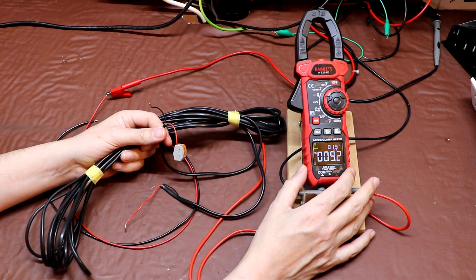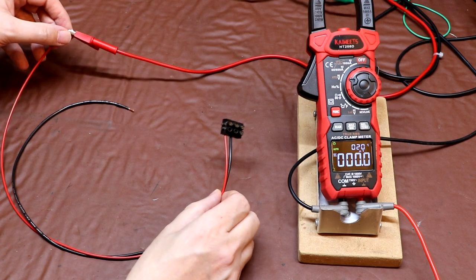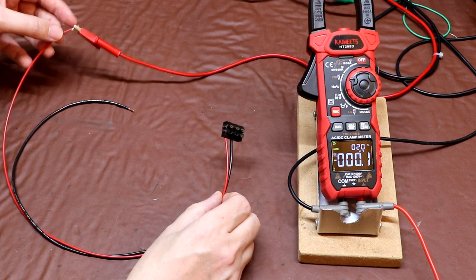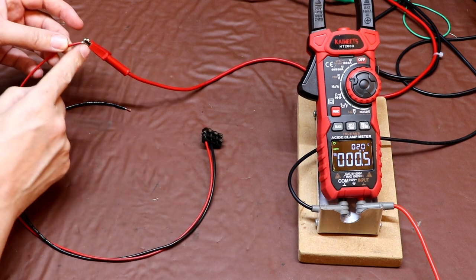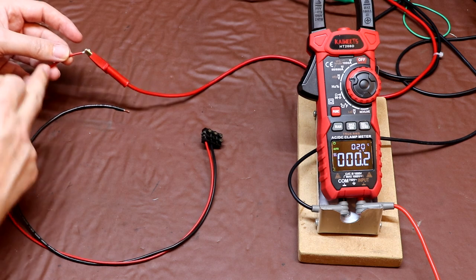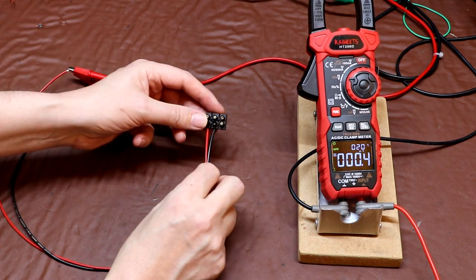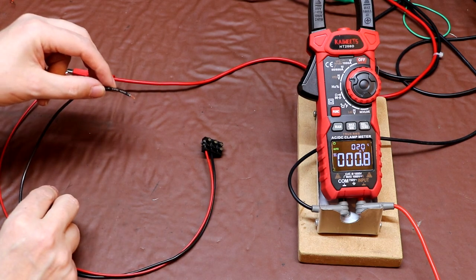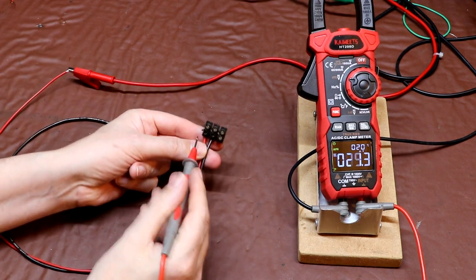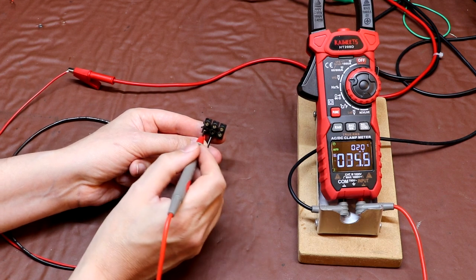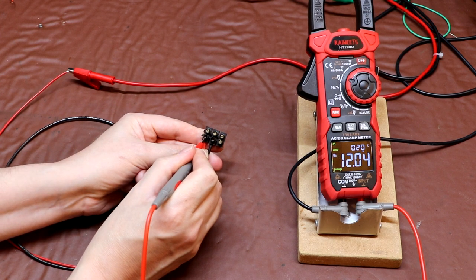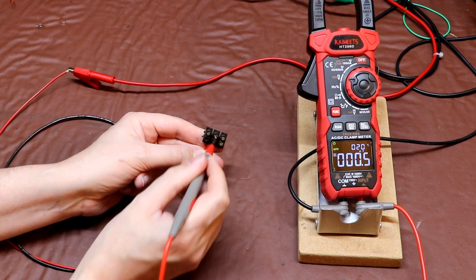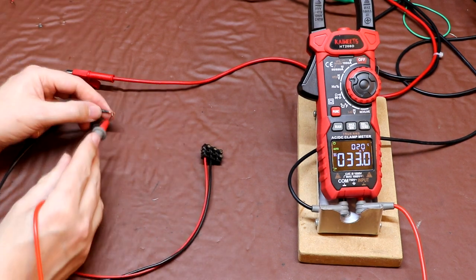But there is a different situation that can occur in DC circuits that can give rise to what we call these ghost or phantom voltage measurements. On the bench here I've got another red and black cable, and as before I've connected the red cable here. That's connected to my 12 volt power supply, and you can see that this runs through to a connector block. Now, the black wire isn't actually connected to anything, so if we take a measurement of the voltage on the connector block here, we're going to see 12 volts. And we're not going to see anything on the black wire, and of course we're not going to see anything on the other end of the black wire either.